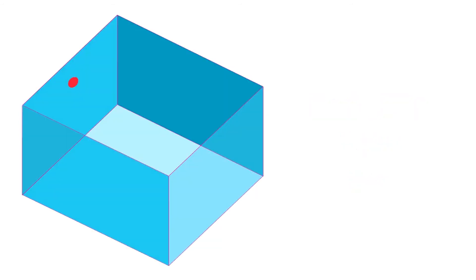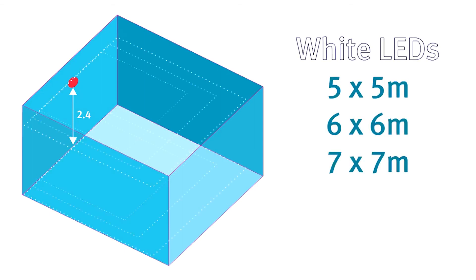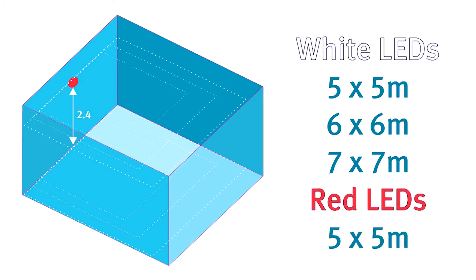For the wall beacons, the coverage volumes are based on a maximum height of 2.4 metres from floor level. So again, subject to your control panel, you can set the coverage to 5 by 5, 6 by 6, or 7 by 7 metres for white LEDs, and 5 by 5 metres for red LEDs.